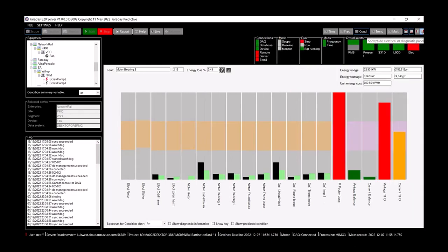The machine condition is shown as green, present and short and long term predictions, because all of these parameters at the left hand side, the ones with the brown bars, are green. The machine has the capability of detecting maybe 40 different failure modes. It only displays those that are relevant to this machine. We can see they're all okay, both at present and in the future.